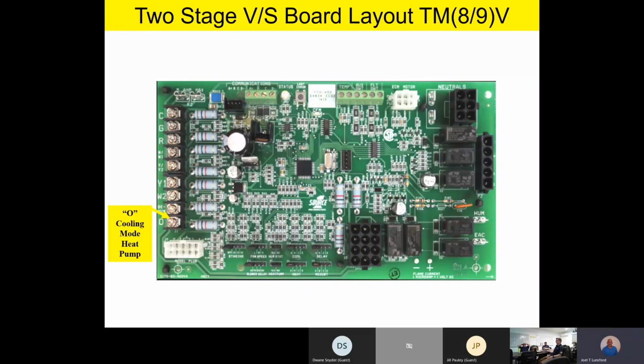The O terminal is going to be for the cooling mode of operation on our heat pump product if you have a dual fuel product. Now, this is really important. If you're not going to put this on a heat pump, there's a jumper you're going to have to select that says AC or heat pump. It comes from the factory on AC. However, we have had some field calls in the years of experience I've been with Johnson Controls, where we had one or two boards, maybe a replacement board, that was on the heat pump jumper.